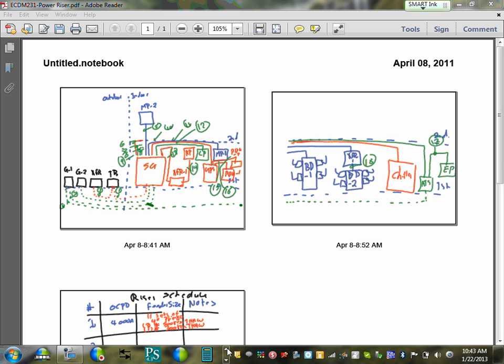So this MP1 would be our NF type panelboard. If you go to 9-13, that's where our NF type panels start. Normally, if it's being fed from this gear, this would be main lug only. So 600 amp main lug only. At the very top of the page of 9-13, that first table, 9-46, those are main lug, and then you go down to hit 600 amp.